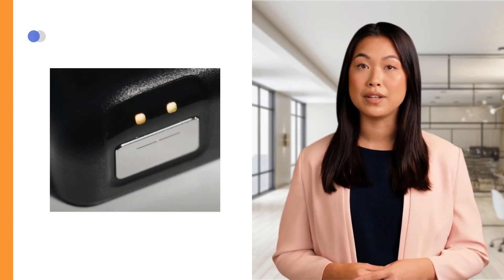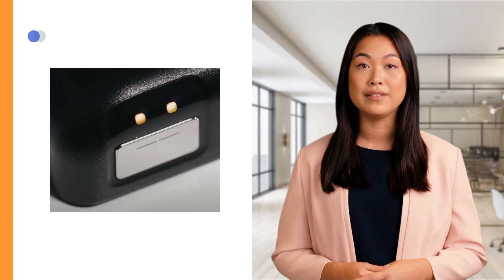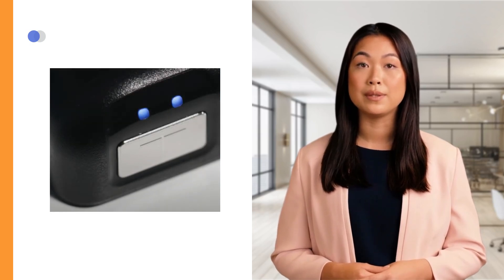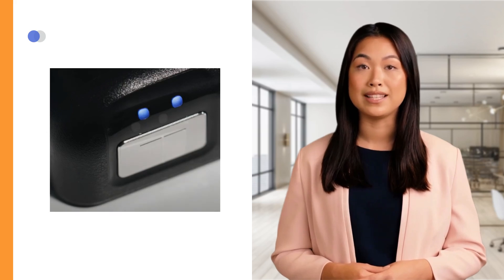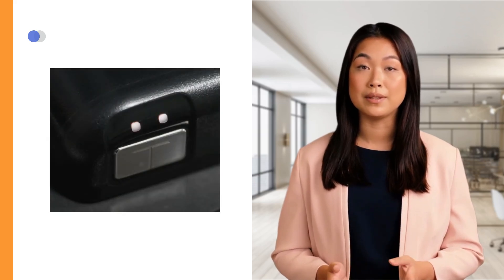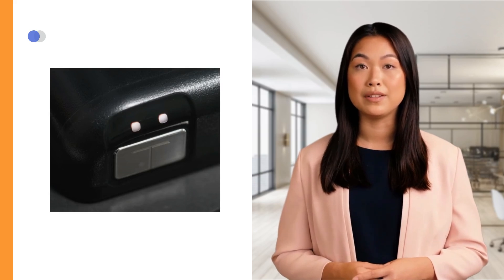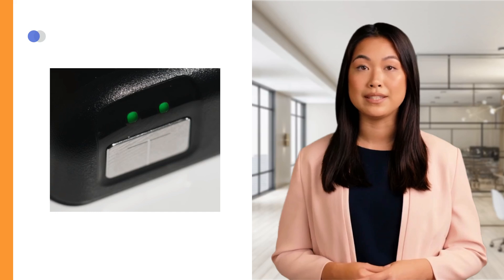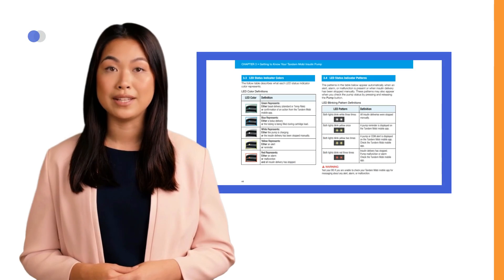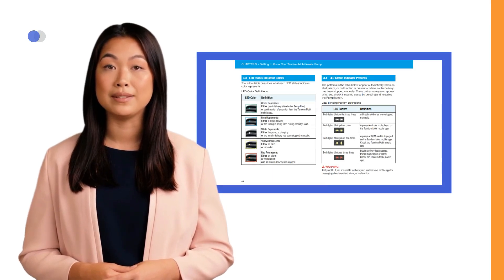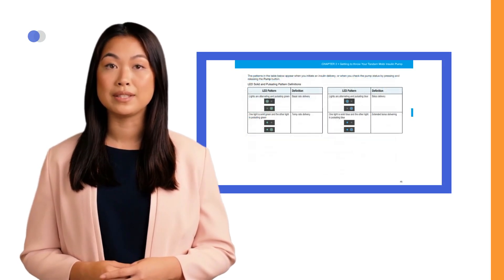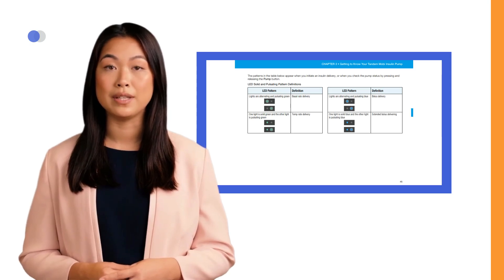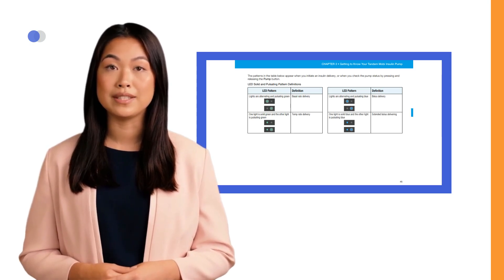Yellow represents an alert or a reminder such as a sensor expiring soon or low battery. Blue represents bolus delivery or the tubing being filled during the cartridge loading process. White represents either that the pump is charging or insulin delivery has been stopped manually. Green represents basal delivery or a temp basal rate is being delivered. Refer to your user guide to learn more about the pump status lights blinking patterns. Understanding these components and indicators will ensure you can effectively manage your insulin delivery with the Tandem Mobi insulin pump.